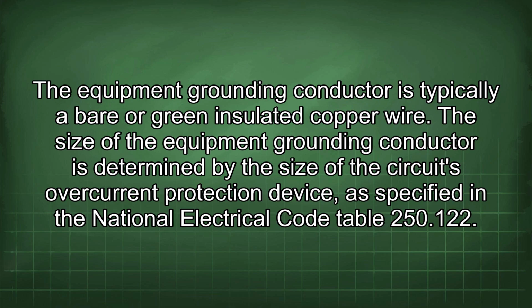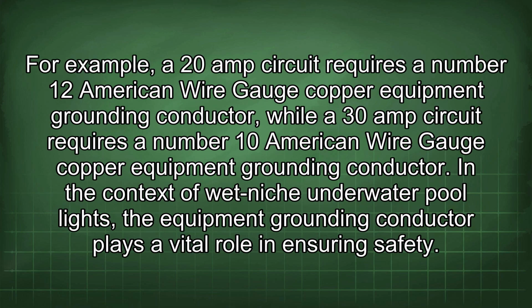The size of the equipment grounding conductor is determined by the size of the circuit's overcurrent protection device, as specified in National Electrical Code Table 250.122. For example, a 20 amp circuit requires a number 12 American wire gauge copper equipment grounding conductor, while a 30 amp circuit requires a number 10 American wire gauge copper equipment grounding conductor.